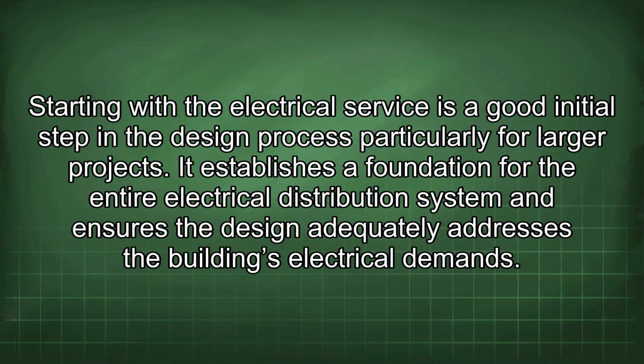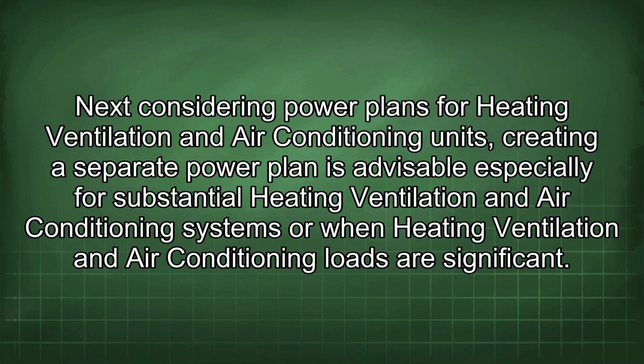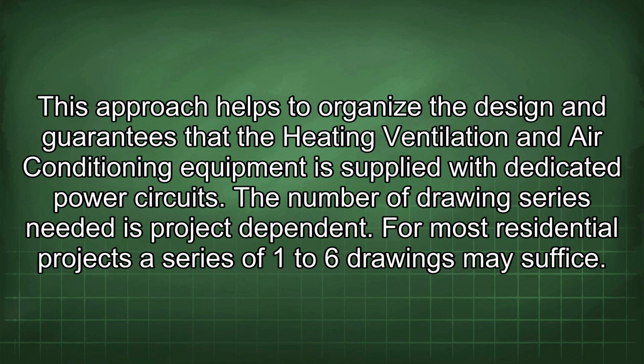Starting with the electrical service is a good initial step in the design process, particularly for larger projects. It establishes a foundation for the entire electrical distribution system and ensures the design adequately addresses the building's electrical demands. Next, considering power plans for heating, ventilation, and air conditioning units. Creating a separate power plan is advisable, especially for substantial heating, ventilation, and air conditioning systems, or when heating, ventilation, and air conditioning loads are significant.